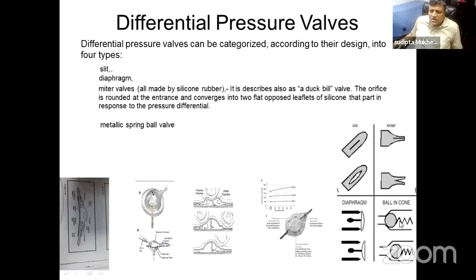So this is the widely used slit and spring valve. Actually, it is used by Chhabra Surgiware. The shunt name is Chhabra shunt. You see the upper one, there is a plastic housing, with an inflow side, plastic housing, and outflow. Within the plastic housing, another plastic tube is there. Within the second plastic tube, there is a steel spring. In the second plastic tube, there are four longitudinal slits. That is the mechanism which causes it to open after a pressure difference.